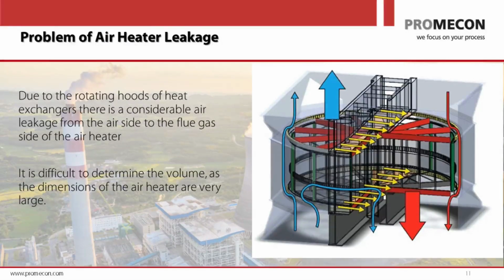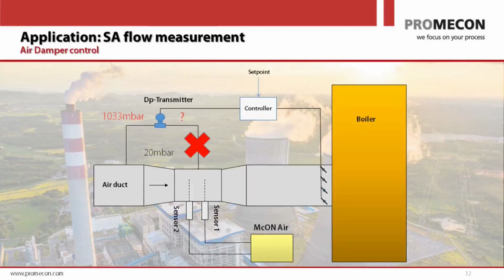So we can basically say all the airflows that go into the boiler, as soon as they're preheated by a rotary air heater, they carry a lot of ash. And this ash, just by coincidence, has a negative effect on the machine itself. The ash can be abrasive. The ash can also lie in the bottom section of the ducts. But most of all, the ash is impacting the ability to measure the airflow itself. And why that is a problem, we see on the next slide.